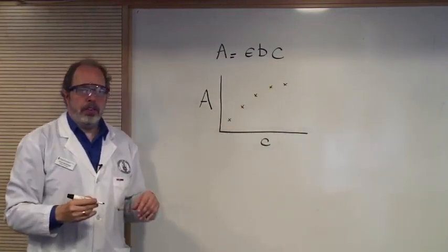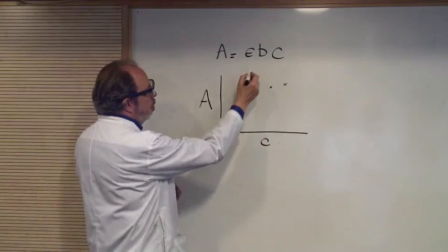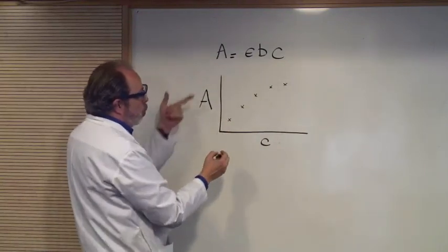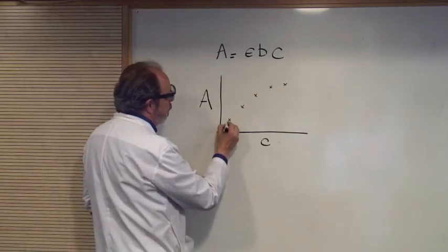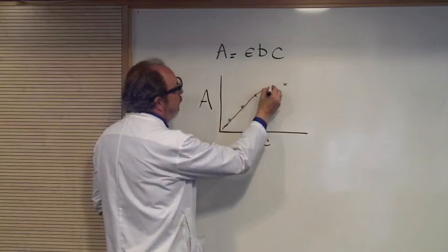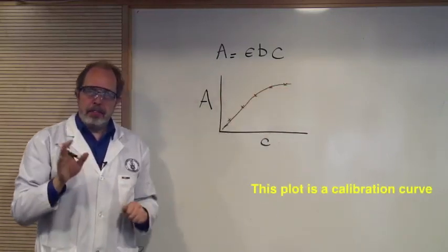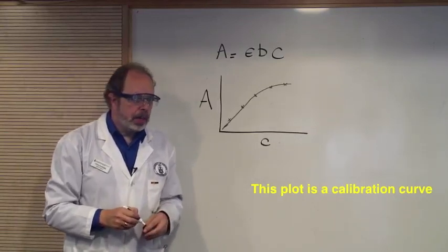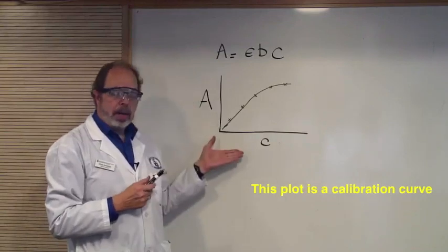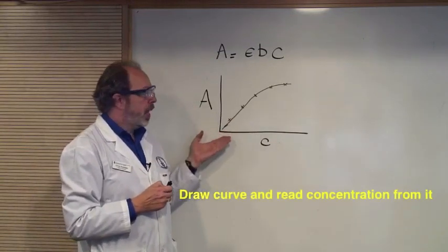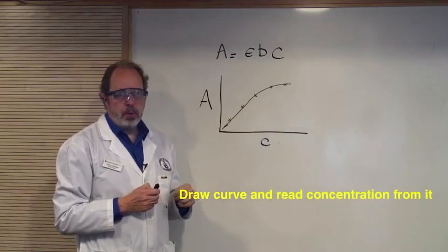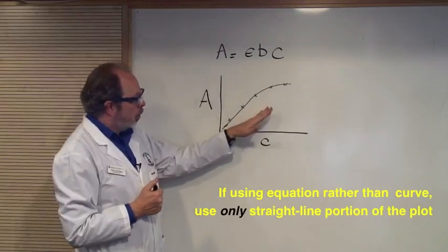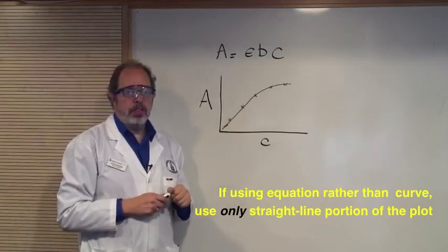As you can see, we're going to get a curve here. Beer's law says this will be a straight line. It's y equals mx plus b. And the slope will be epsilon b. Now, the first part of this line is indeed a straight line. But after that, it starts to flatten out. That frequently happens at higher concentration. It means that Beer's law is not strictly being observed, but you've still got a calibration curve. And if you can draw this, you can use the data even in the curved portion. However, if you want to use a mathematical relation of Beer's law, A equals epsilon bc, you can only use the straight line portion of the curve.